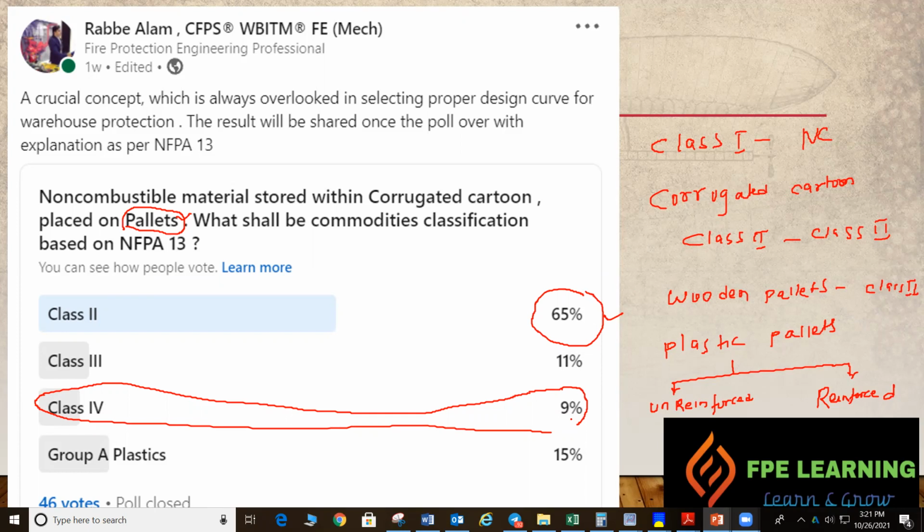So as the oxygen goes on, the material burns until all the plastic burns itself, right? All the mass goes off. So if you select class 2, there is a high chance, around 80% or more, that the fire is not going to be extinguished because the heat release rate is much higher than how much water we get from the ceiling sprinklers if it is kept on the floor, right?